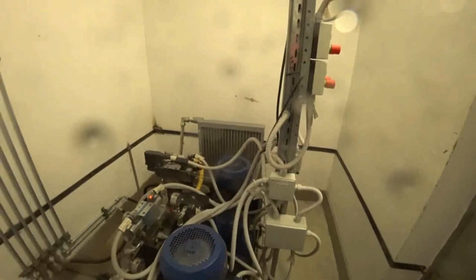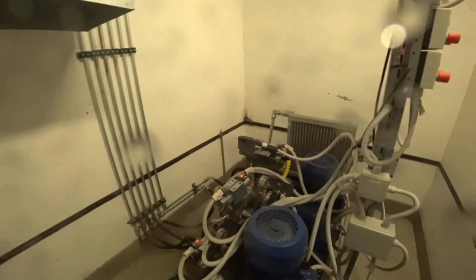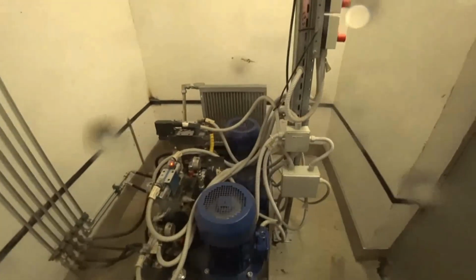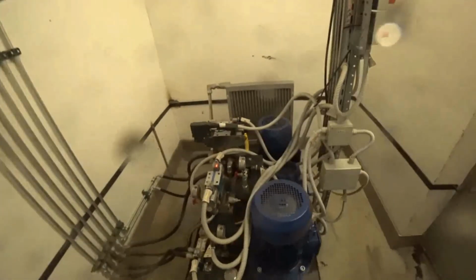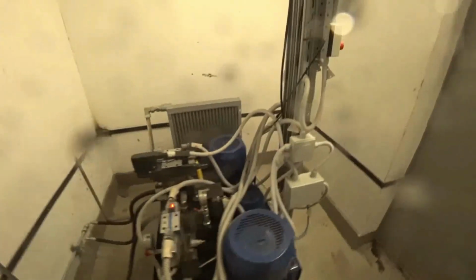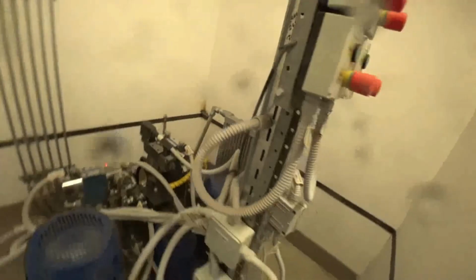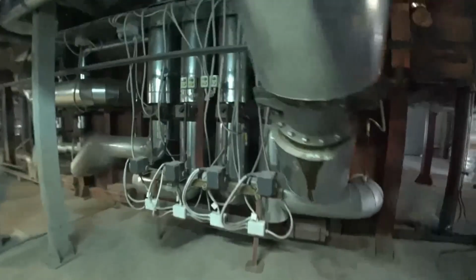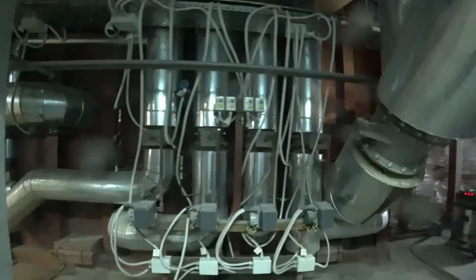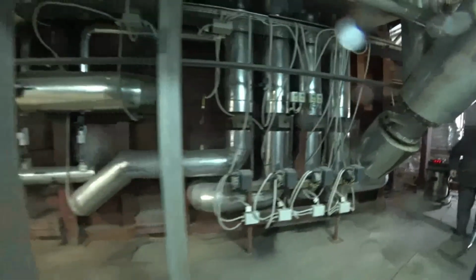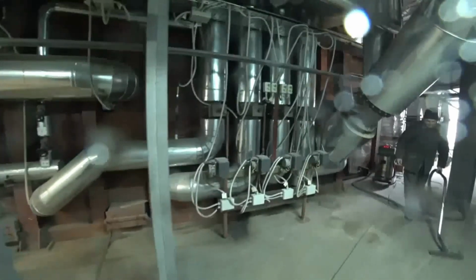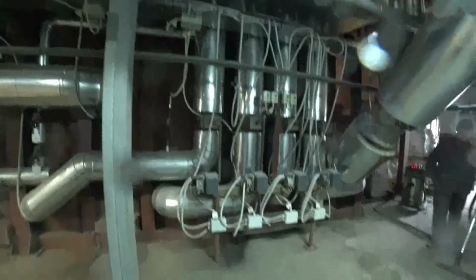Next is the room in which the main hydraulic station of the steam boiler is installed. This station controls the hydraulic cylinders of the inclined pushing grate. Seamless stainless steel pipes are used for oil pipelines. Now, in front of you is the primary air distribution unit for different air zones of the combustion device. The unit, as well as the fan, is equipped with devices for automatic regulation of airflow.